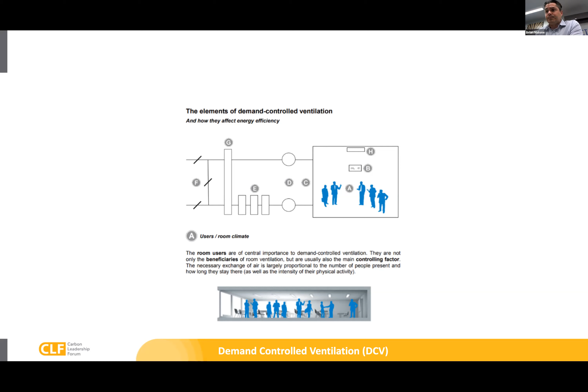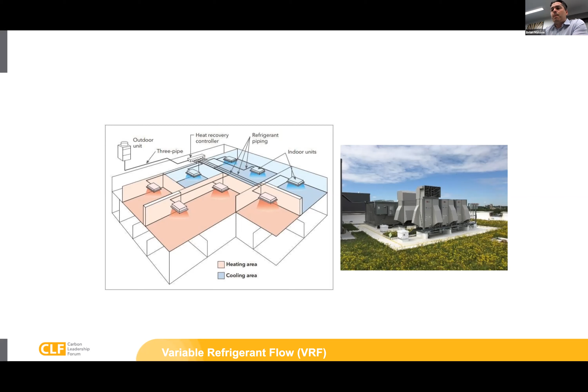We do have an air source VRF system, as I had mentioned. The air source VRF system does have simultaneous heating and cooling, and it does improve the efficiency of the VRF system, especially during the swing seasons when some spaces are going to be in heating and others are in cooling, and you can transfer heat around the building. One other thing about the design is we were very cognizant of being able to provide heat to the space in the event of a power outage or in the instance of a compressor failure. And we made sure that our DOAS systems were able to compensate in those emergency scenarios.